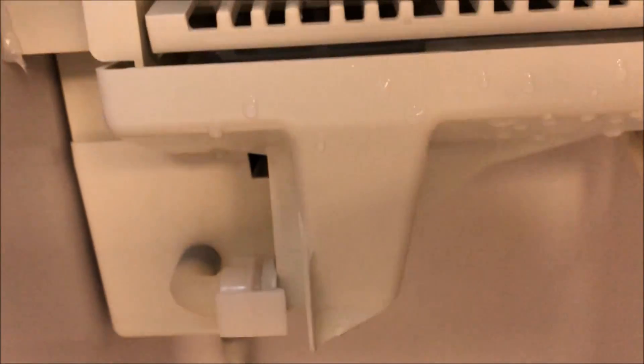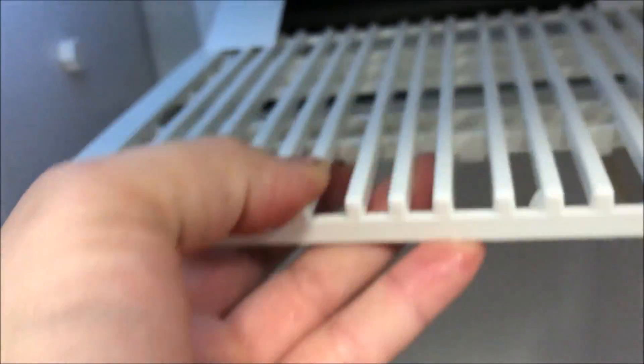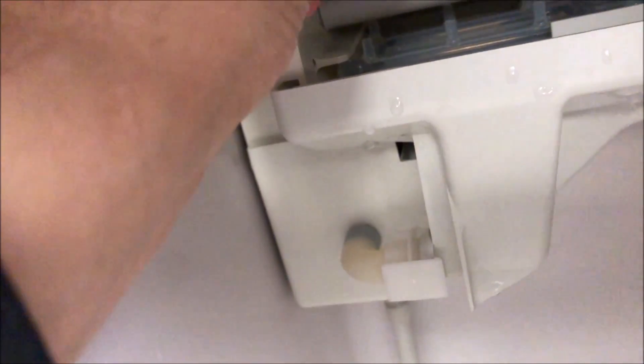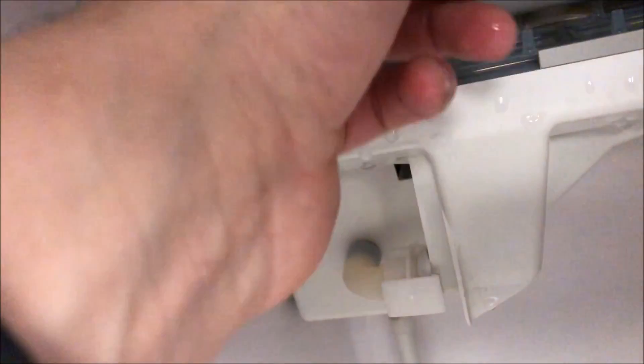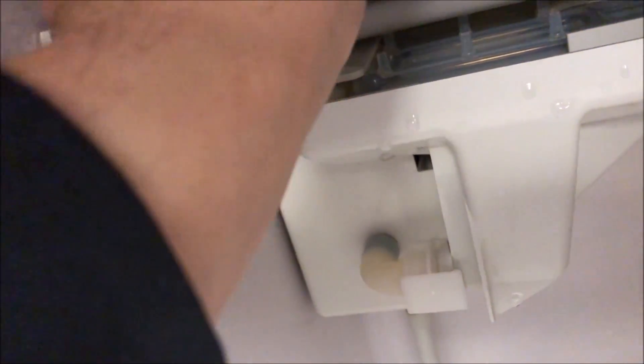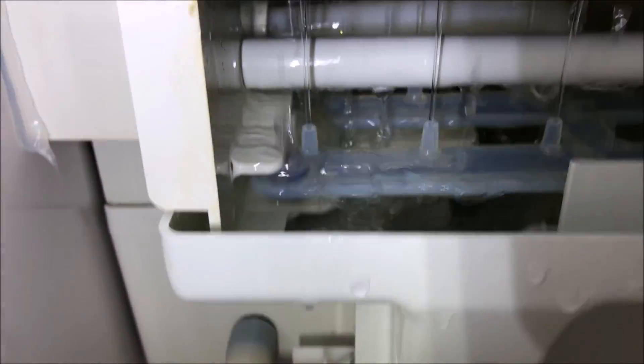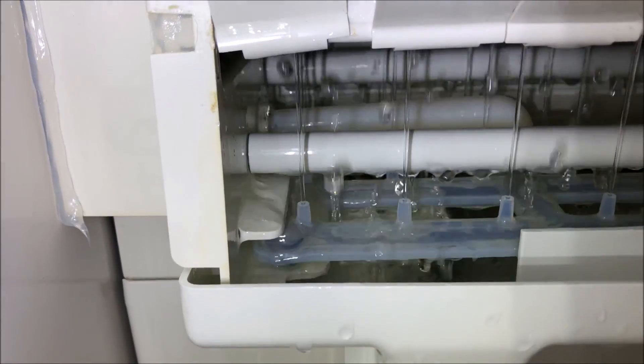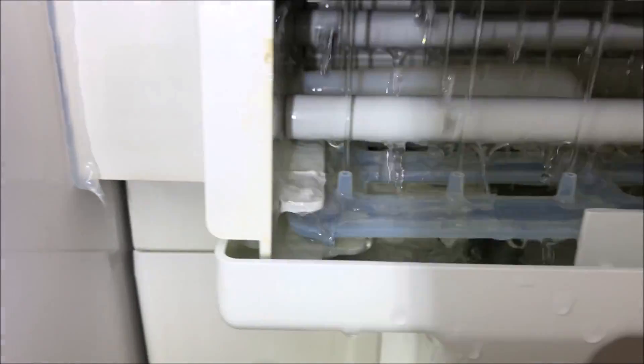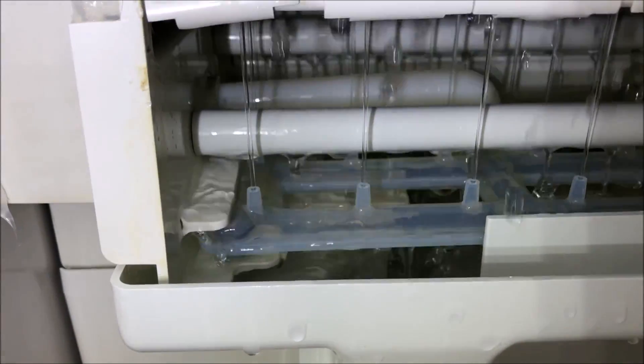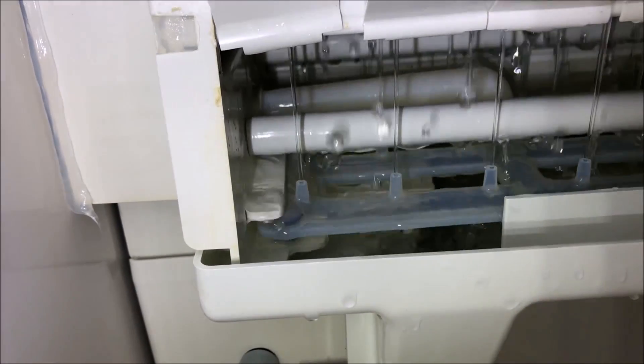Let's carry on with our fill cycle here. Let's make sure we're filling up our trough. Let me just pull up these little grids here and let's see if we can see how much water is getting in this trough. And it is filling. You can kind of see it there. Sorry these little tabs keep popping down. But it is filling. It feels like we're at the appropriate level. It's filling quickly. You can see our pumps turning on. So that's telling me that we're actually filling the trough with enough water for the pump to operate.